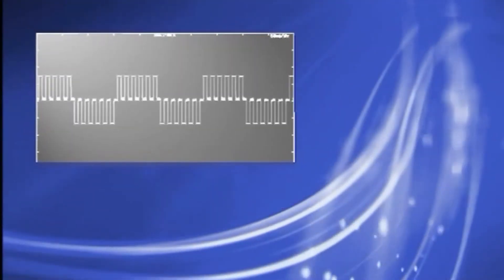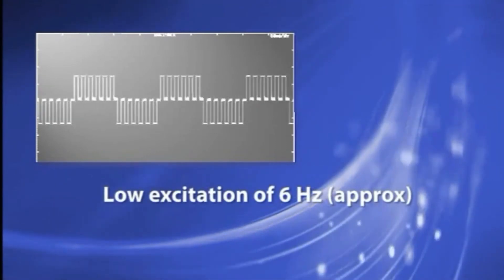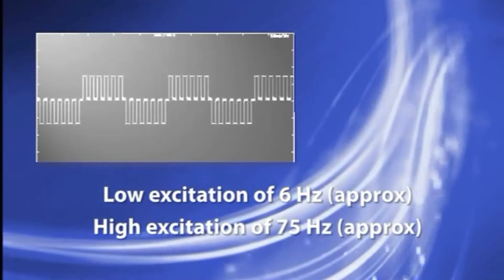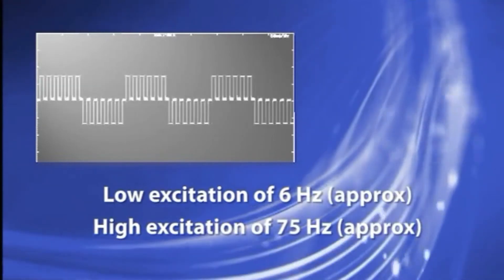The dual frequency waveform can be observed by putting an oscilloscope on the excitation terminals of the Yokogawa ADMAG magnetic flow meter. You can see the low excitation of approximately 6 hertz, the high excitation of 75 hertz, and the two signals superimposed on each other.